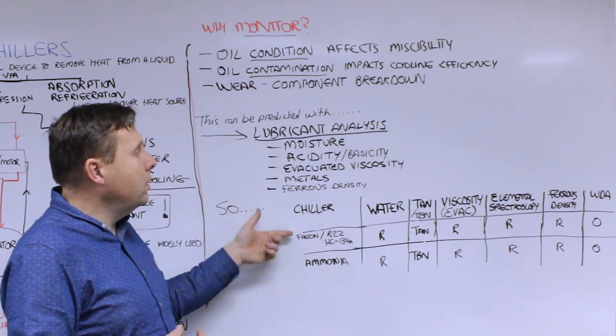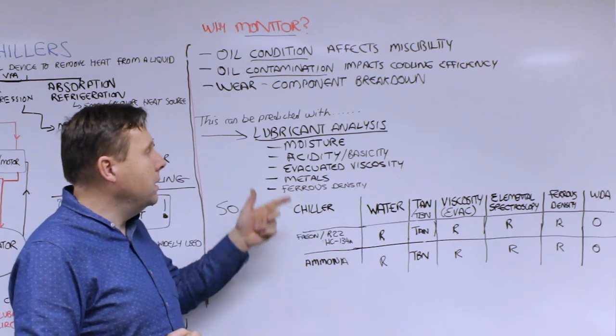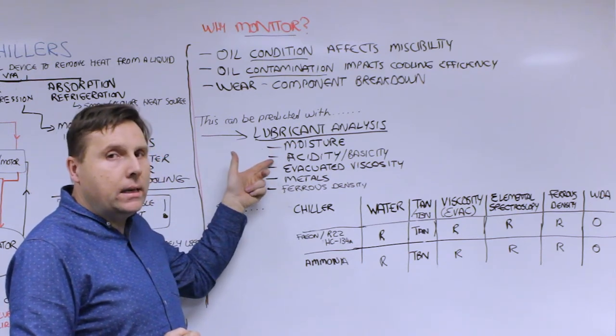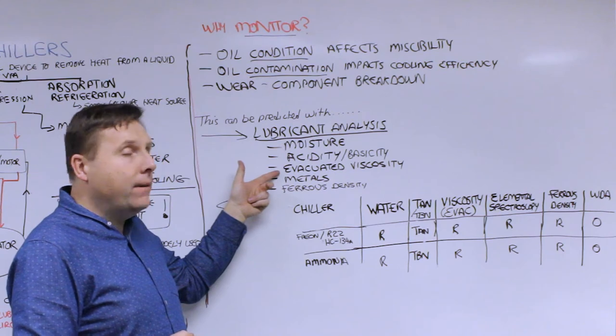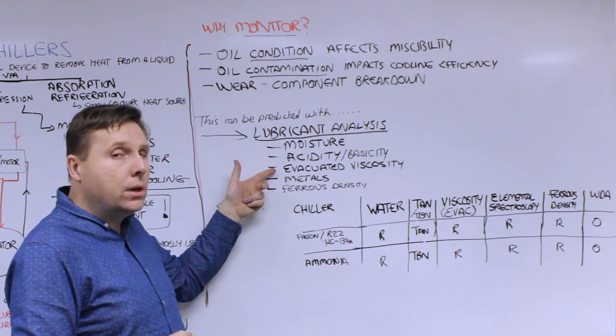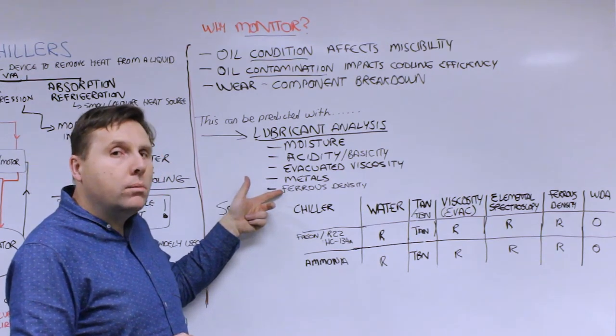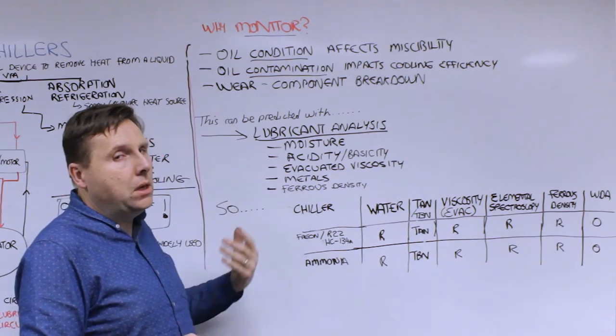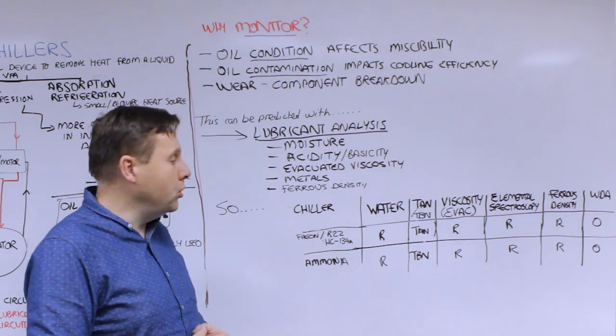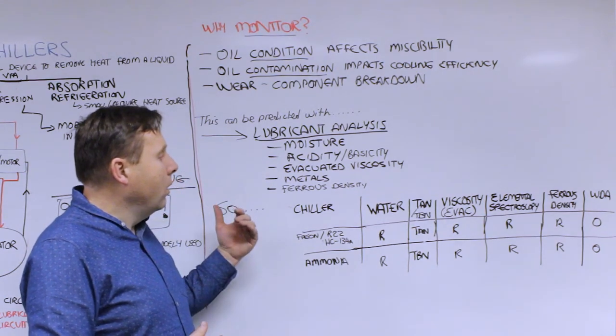The tests that they care about are essentially broken down into a couple of areas: moisture, acidity or basicity, evacuated viscosity at 40 degrees C, elemental metals, and then any large wear debris catch such as ferrous density. Wear debris analysis is an option.